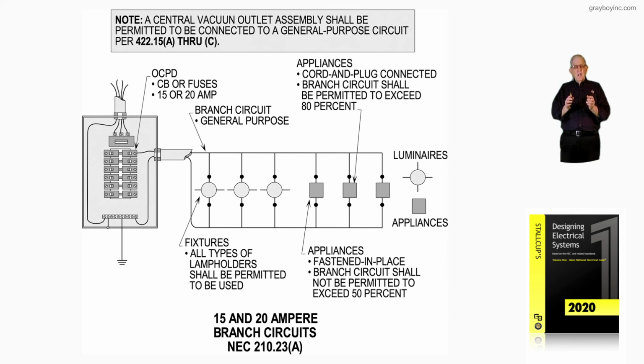So the table takes all this information, all these branch circuit rules, and just has listed in one table everything where you have to derate, loading, and all that kind of thing. So keep that in mind. Know where your Table 210.24 is when you're loading branch circuits with combination type loads such as receptacles, lights, and appliances. And that's what this Figure 14-12 is illustrating.